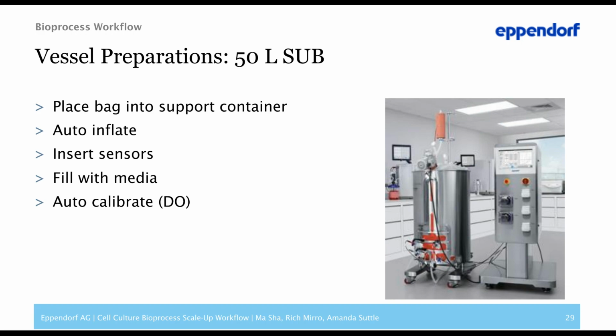I wanted to highlight our vessel preparations for our 50-liter sub because it's a little bit different than our regular BioBLU single-use vessels. First we unpacked and inspected our bioprocess container. We connected an aseptic pressure sensor to our bioprocess container, which is needed to use the auto inflate and also to detect any pressure within our bioprocess container while running it. We then carefully placed it into the support container, which is pictured to the right. We use the auto inflate feature, which automatically introduces a specified amount of air into the bioprocess container until it's fully inflated, like Rich had mentioned. It also has a built-in safety feature, as he also mentioned, that will shut down all gases in the event of high pressure being detected. So that's really great.